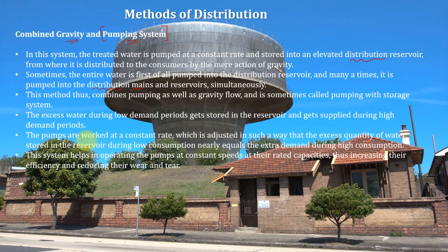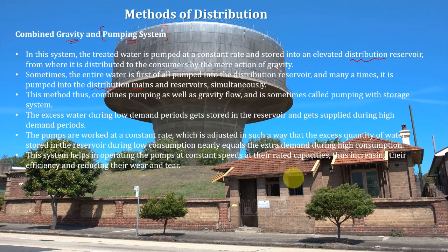The pumps are worked at a constant rate, adjusted such that the excess quantity of water stored in the reservoir during low consumption nearly equals the extra demand during high consumption. This system helps in operating the pump at constant speed at rated capacities, thus increasing efficiency and reducing wear and tear. If the pump is operating only at constant speed, it will reduce wear and tear on the pump as well.